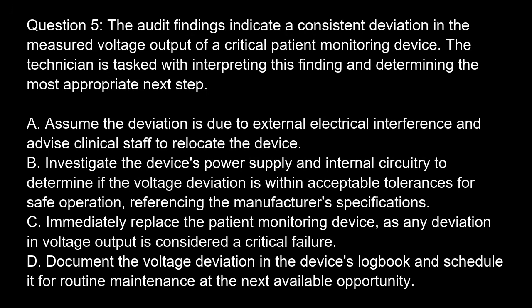Question 5. The audit findings indicate a consistent deviation in the measured voltage output of a critical patient monitoring device. The technician is tasked with interpreting this finding and determining the most appropriate next step. Option A. Assume the deviation is due to external electrical interference and advise clinical staff to relocate the device. Option B. Investigate the device's power supply and internal circuitry to determine if the voltage deviation is within acceptable tolerances for safe operation, referencing the manufacturer's specifications.